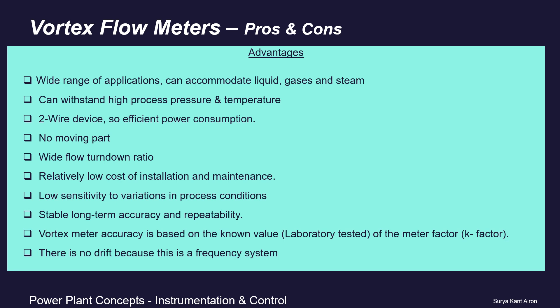The various advantages of vortex flow meters include a wide range of applications — they can accommodate liquids, gases, and steam. They can withstand high process pressure and temperature. Being a two-wire device, they have efficient power consumption. They have no moving parts, a wide turndown ratio, relatively low cost of installation and maintenance, low sensitivity to process condition variations, and very stable long-term accuracy and repeatability.